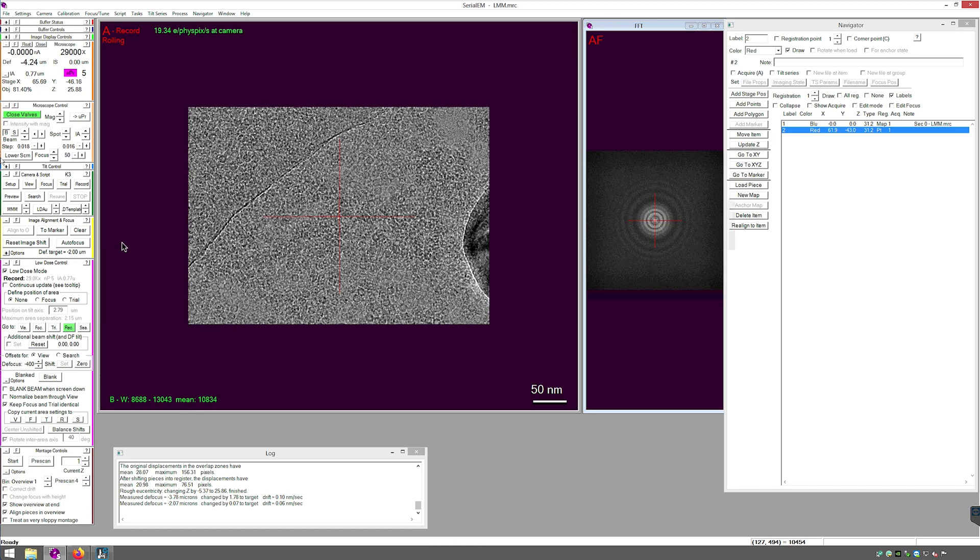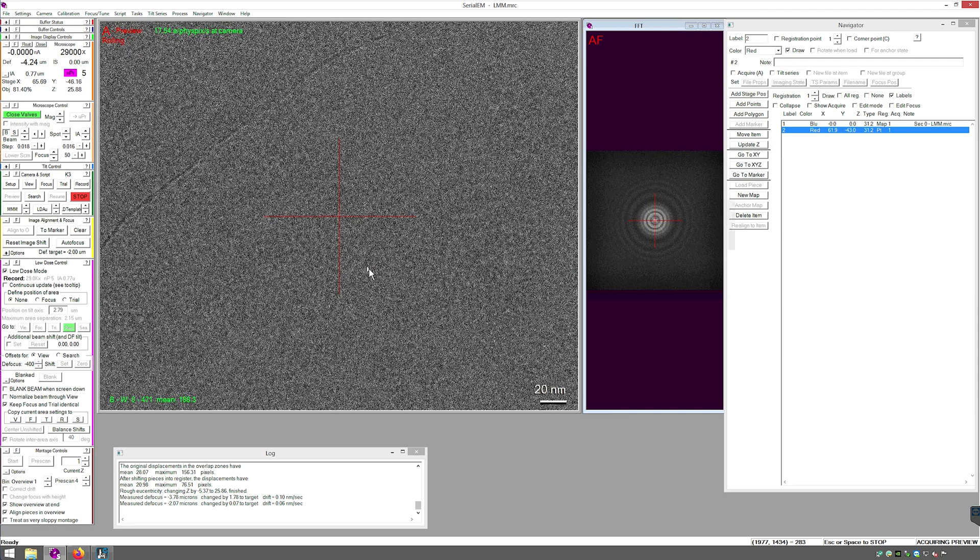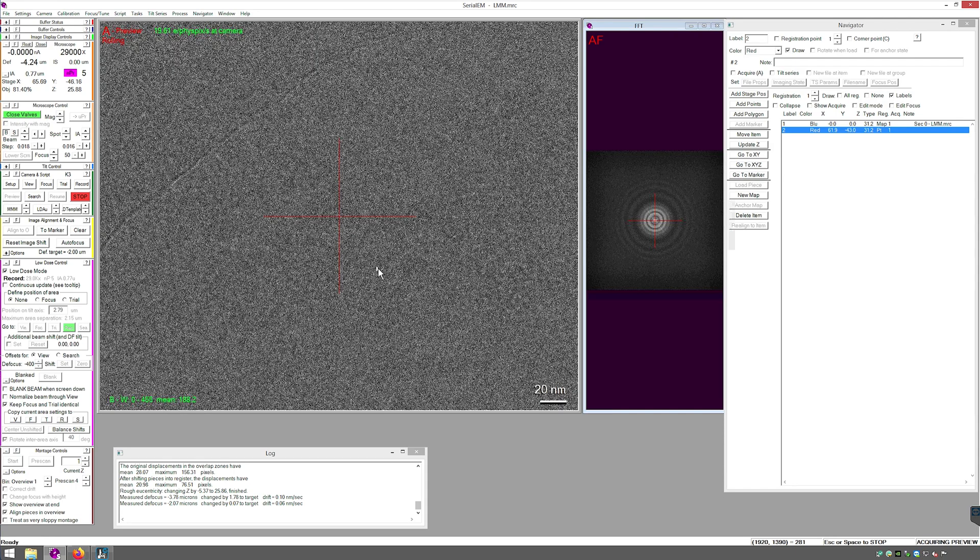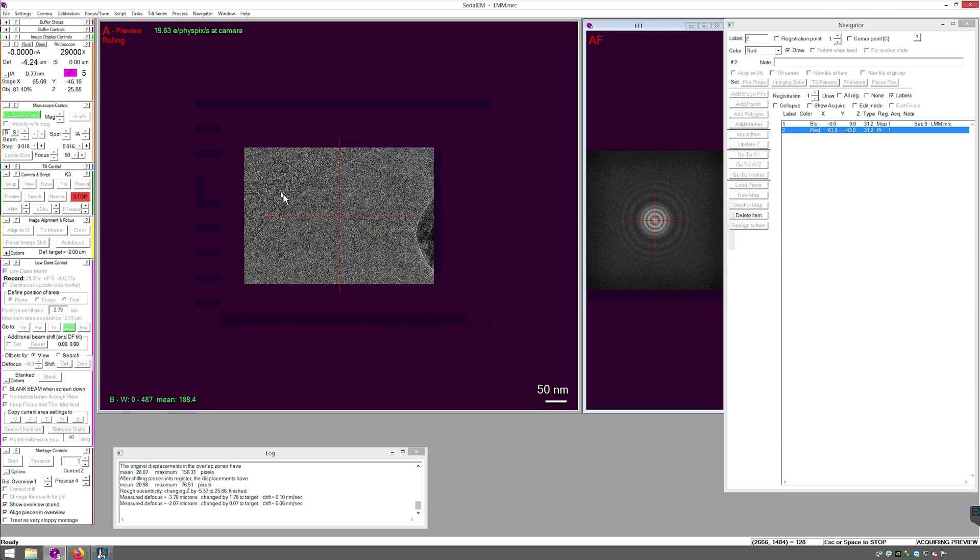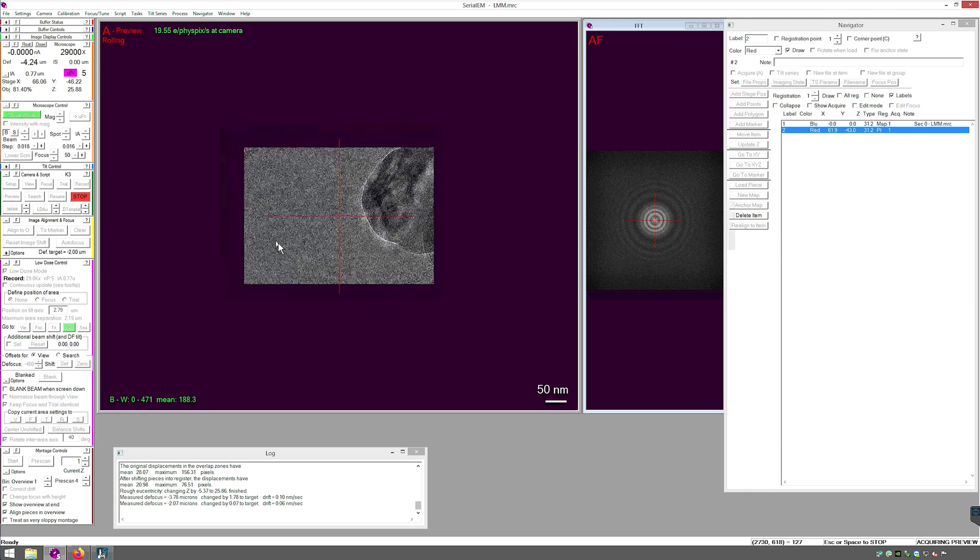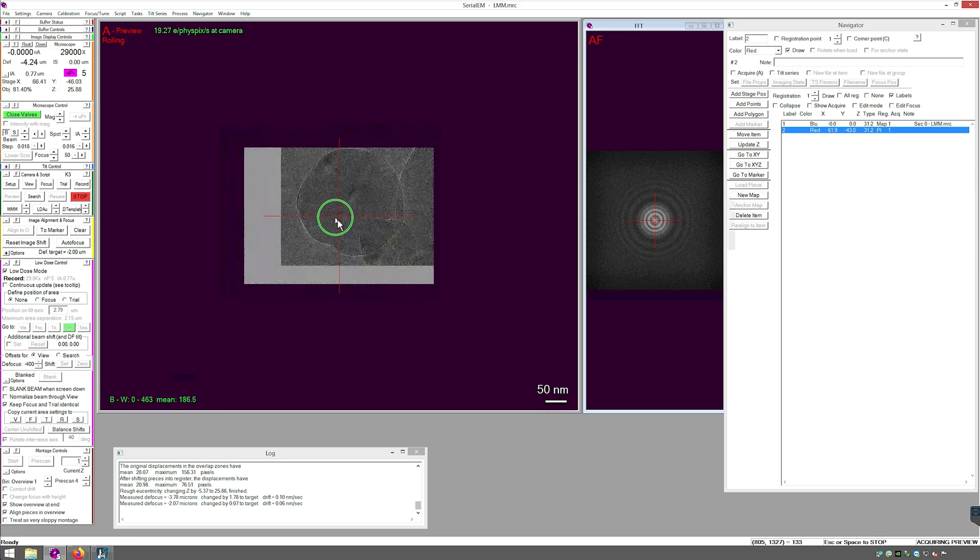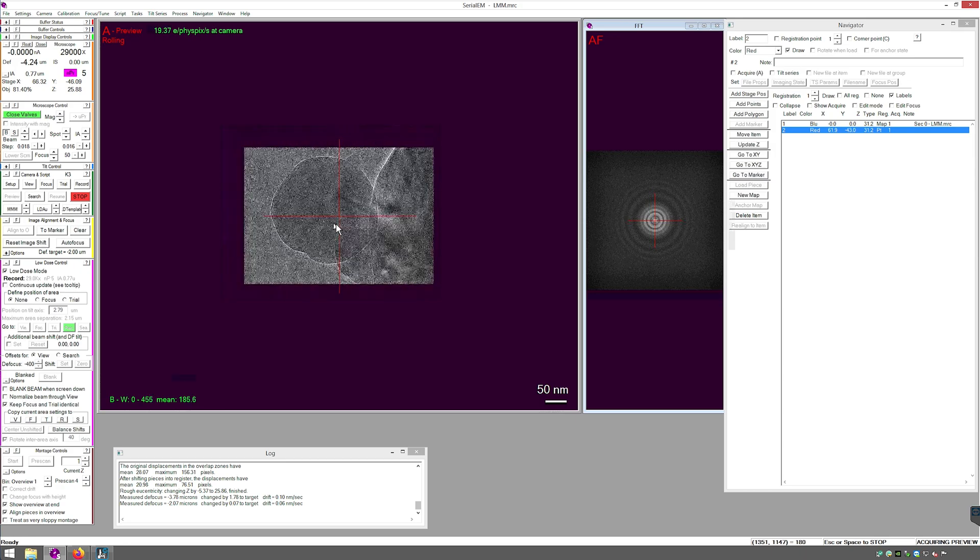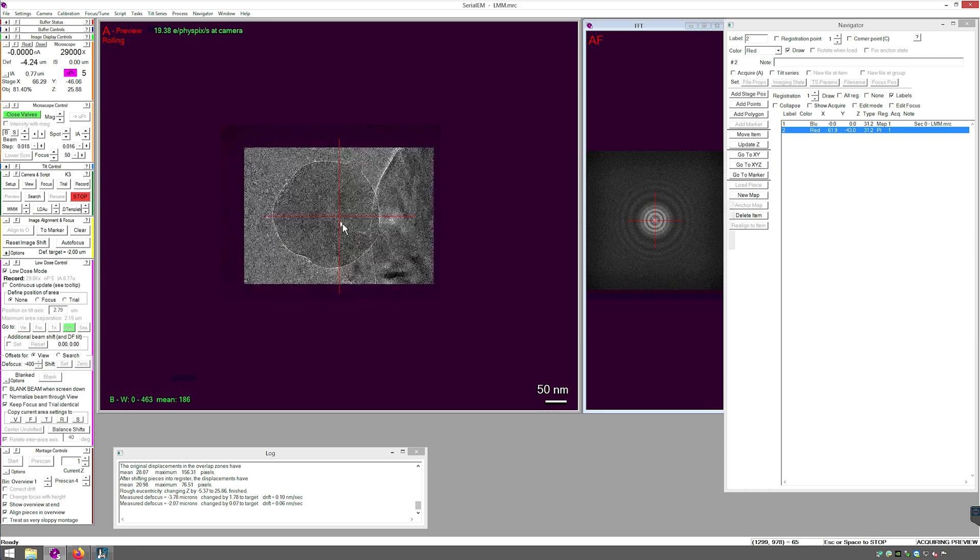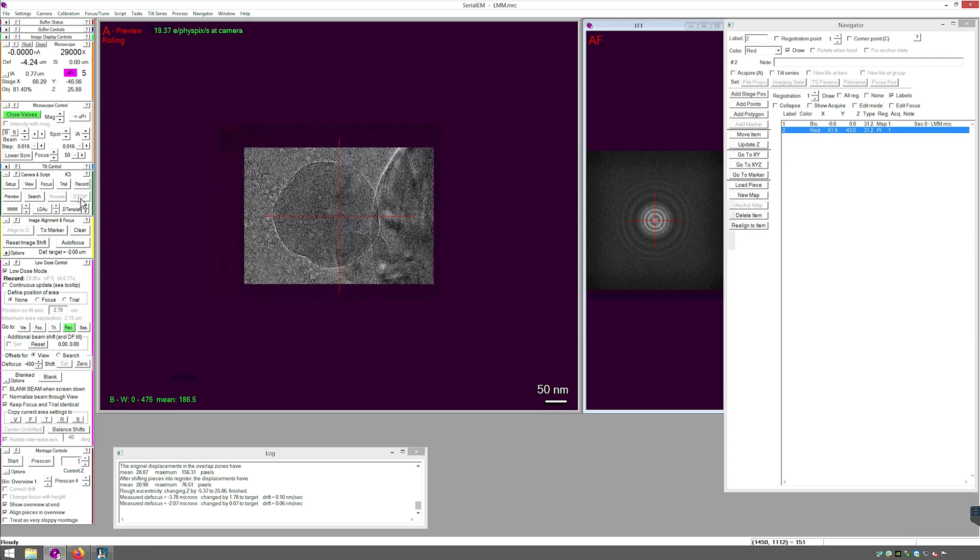Alright, let's see what this looks like in practice. So you'll see right now that I have a record image with a piece of contamination to the right. I'm going to use preview, which is a live record image. And I will move the stage over to that piece of contamination. So I'm going to move over there and I'm going to center it as well as I can while being mindful of the fact that it will melt. Click stop to stop the live view.